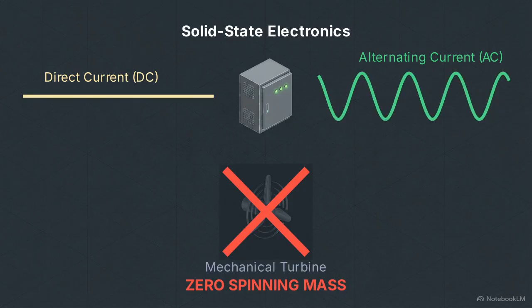Beyond the frequency, there is a thermal bottleneck. According to the power loss equation, power loss equals current squared times resistance. The actual capacity of a transmission line is dictated by heat rather than volume. Injecting gigawatts of remote wind power into existing infrastructure pushes the current well past the thermal limits of legacy aluminum and steel cables. The metal physically heats up, expands, and sags toward the ground, which can lead to phase-to-ground faults.